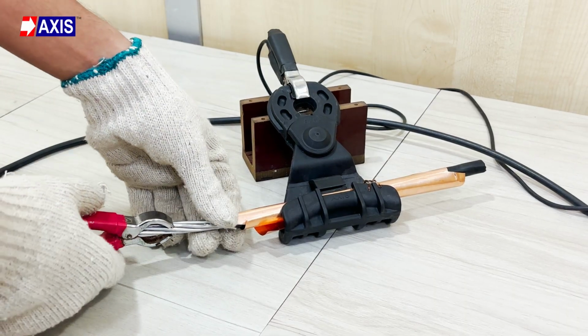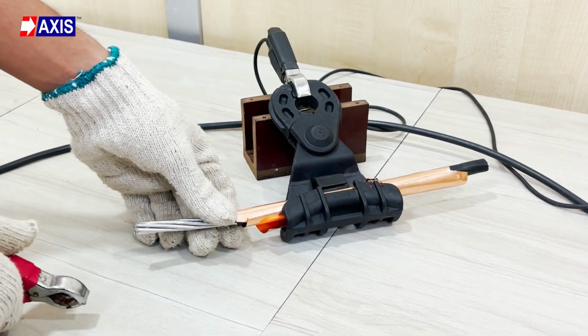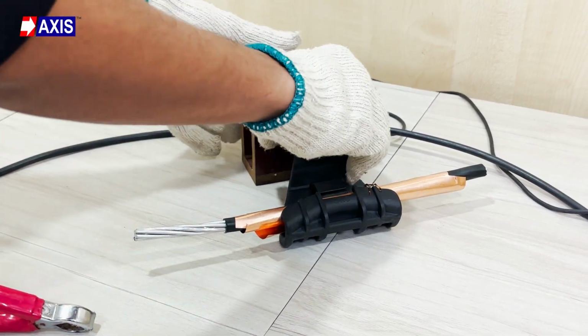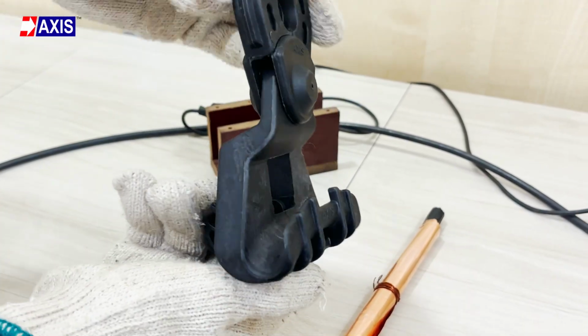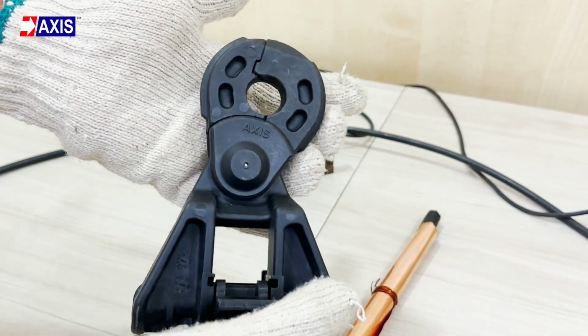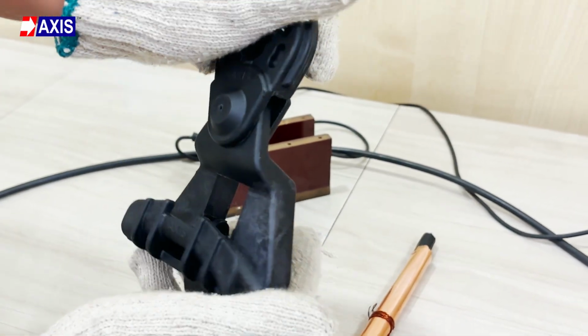As you can see, the Axis suspension clamp completed the test without any failure. This confirms that the clamp maintains dielectric integrity and electrical insulation under service conditions.